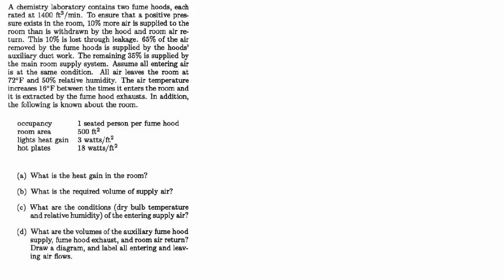101 Solve Mechanical Engineering Problems, HVAC-12. A chemistry laboratory contains two fume hoods, each rated at 1400 CFM. To ensure that a positive pressure exists in the room, 10% more air is supplied to the room than is withdrawn by the hood and room air return. This 10% is lost through leakage. 65% of the air removed by the fume hoods is supplied by the hood's auxiliary ductwork.